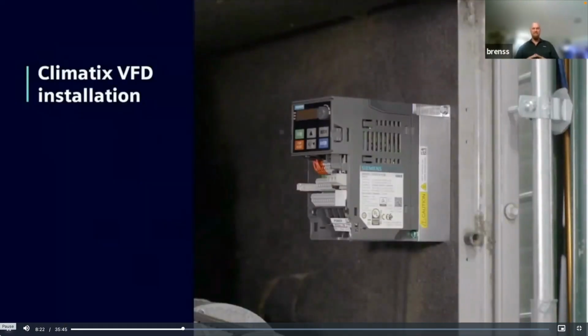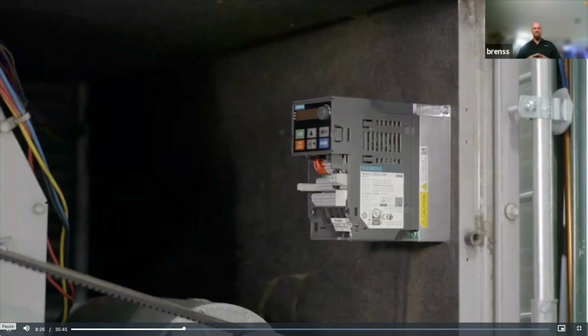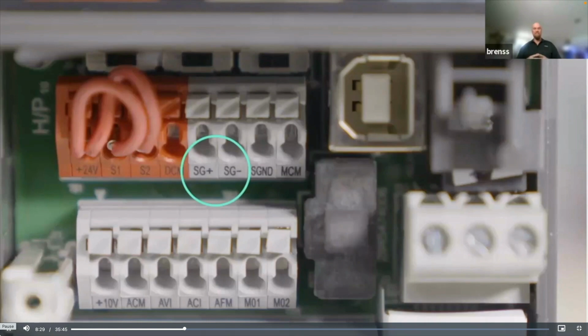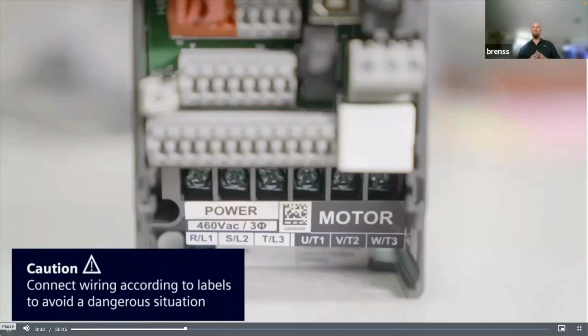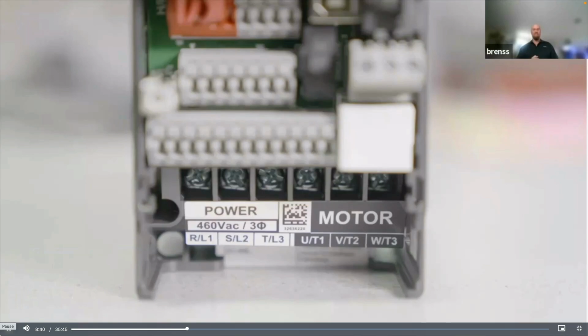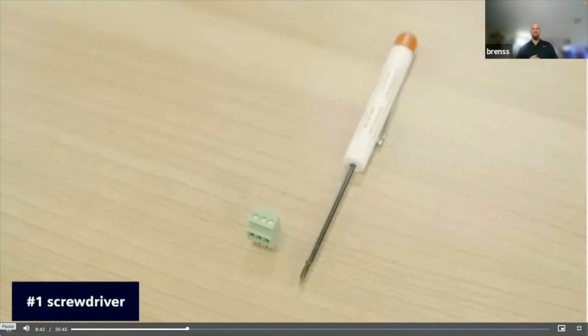If a Climatix variable frequency drive is part of your solution, mount it near the fan. Pay attention to the positive and negative markings on the SG terminals. And be sure to connect the power and motor wiring to the correct lugs according to the labels to avoid a dangerous situation. Here you will use the number 1 screwdriver.